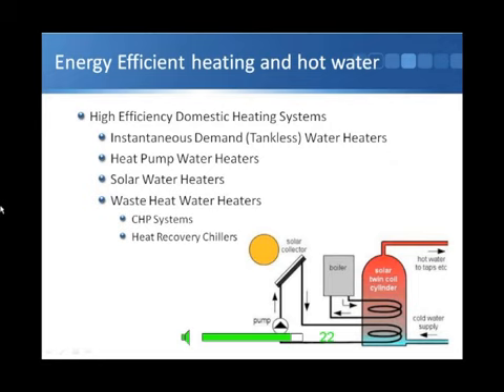So on the heating side, we've really got to think about heating very carefully. And what I have found with higher levels of insulation in buildings, the hot water loads are becoming fairly dominant, certainly in accommodation, residential, hotels, and those sort of buildings. Offices, of course, hot water is still not a particularly big load, but we may find that hot water in many buildings is a bigger heating load than heating itself. And there's various ways of looking at that, whether we have heat pumps to provide the heating and hot water for us, whether we integrate it with solar hot water heating, and whether we get waste heat from things like combined heat and power systems or heat recovery chillers.